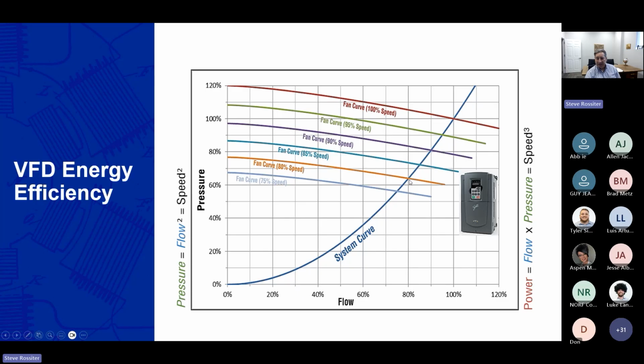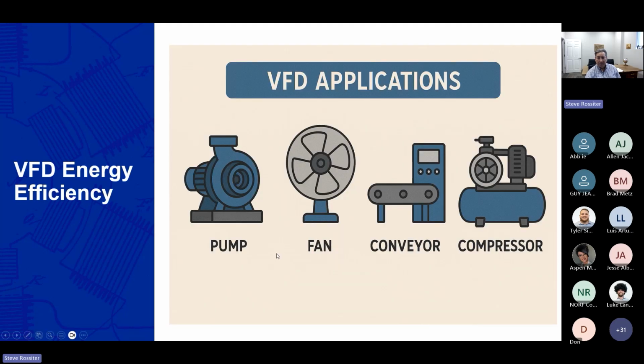I don't need as much pressure to operate at that point. But the real magic is power reduces as a cube of speed, theoretically. So I'm looking at 80% load or 80% speed, reducing the horsepower required by almost 50%. And of course, any kind of process that doesn't need to always have full speed is going to be greatly enhanced with something that can reduce the speed of that motor and thereby get that natural law of following the affinity laws of reducing the horsepower requirements tremendously. So as that technology started becoming a little bit more mature, the applications for variable frequency drives just skyrocketed. Pumps and fans being probably the predominant ones because every building or every industrial process with a centrifugal pump or fan are going to have huge savings.